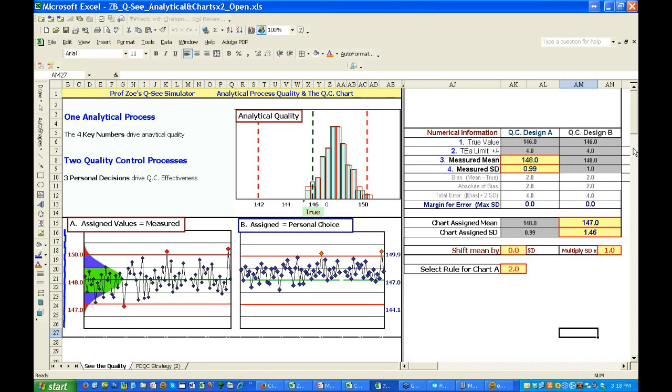and then once those are addressed, then I'm going to load up on QC so I can have enough of a history to start figuring out where I am with the method, where I am with this current situation, and then create the appropriate Levey-Jennings chart that reflects the current Gaussian distribution so that I can effectively determine if my instrument remains stable or unstable based on the rules that I've selected.